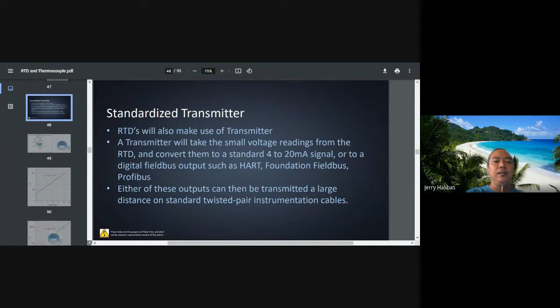But this time, if it is a transmitter, then it is a standard 4 to 20 milliamps signal output. You no longer use the other standards, such as 0 to 20, or 0 to 5 volts. You know the meaning and the reason, no? And if you can add additional digital communication, then you could add HART. I will discuss what a HART protocol is.